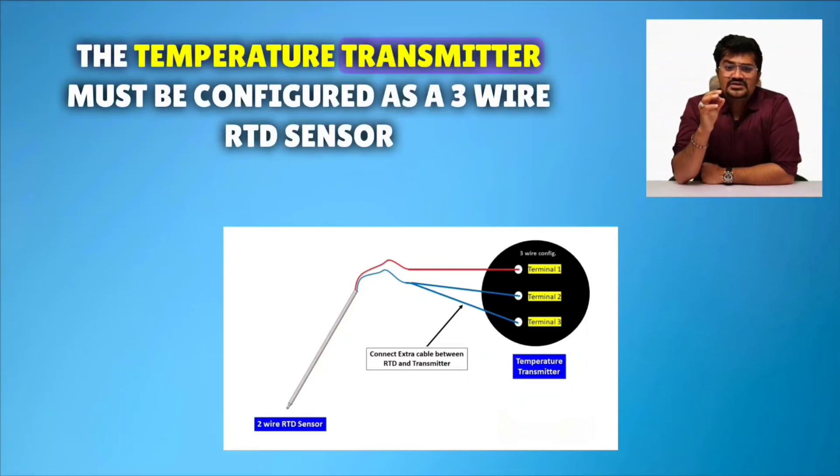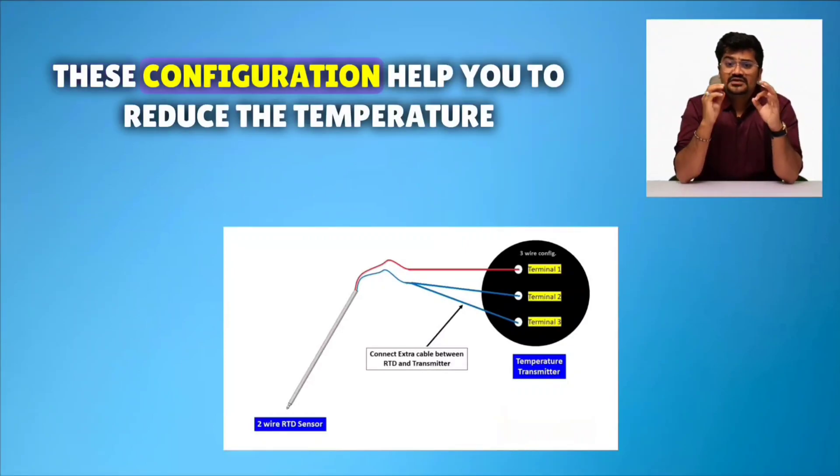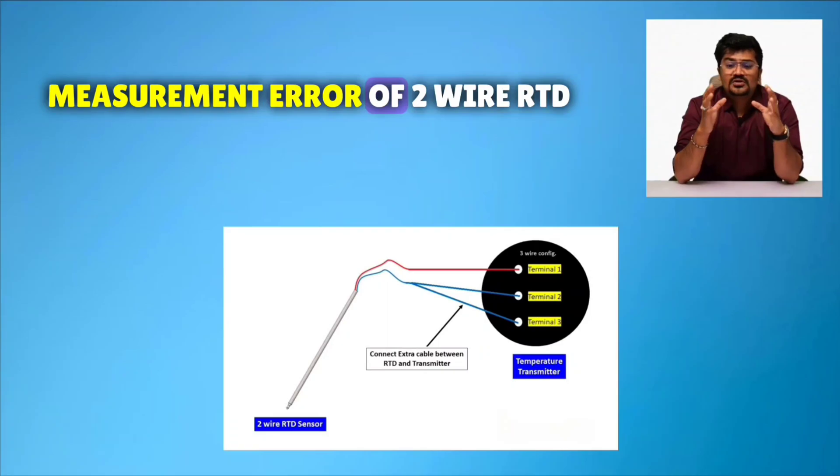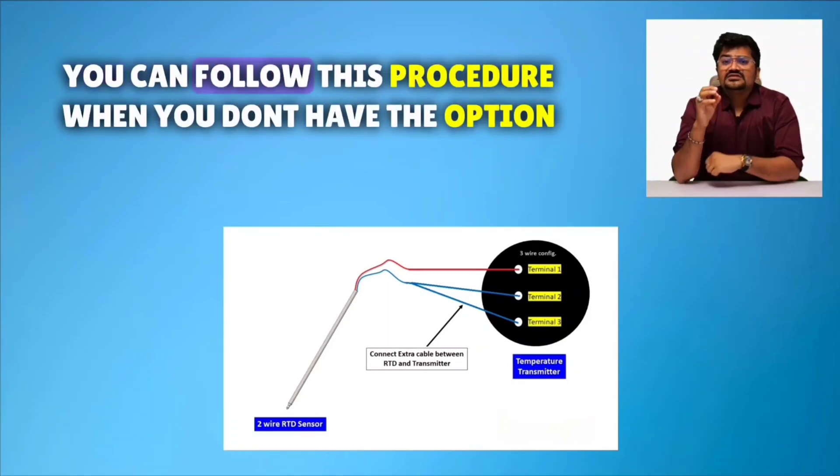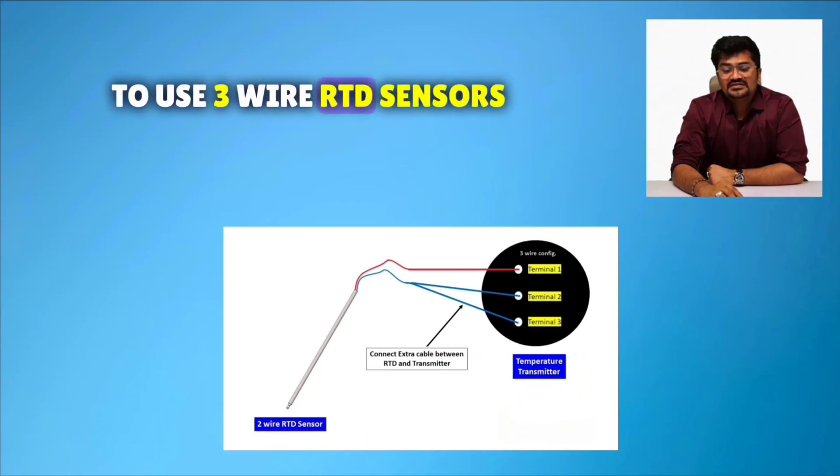The temperature transmitter must be configured as a 3-wire RTD sensor. This configuration helps you to reduce the temperature measurement error of 2-wire RTD. You can follow this procedure when you don't have the option to use 3-wire RTD sensors.